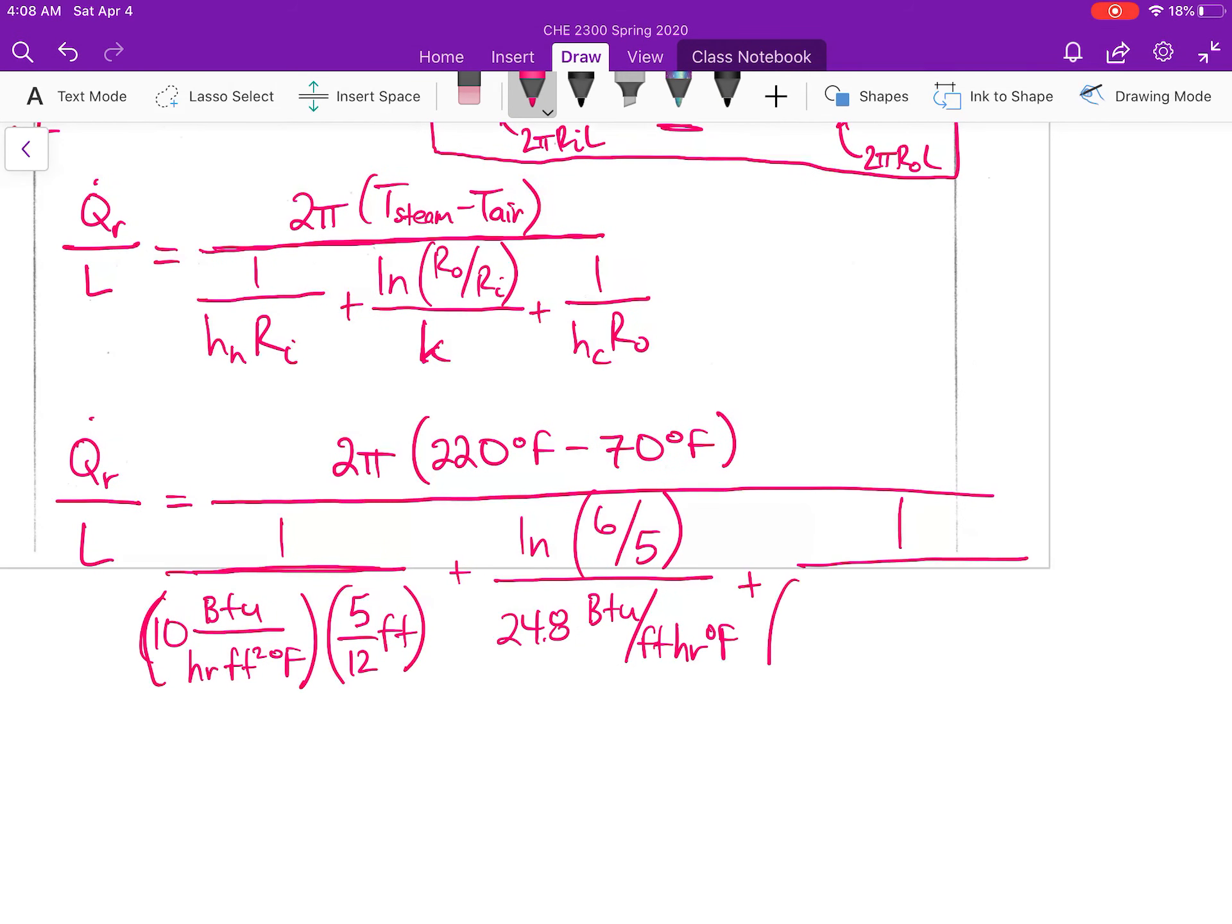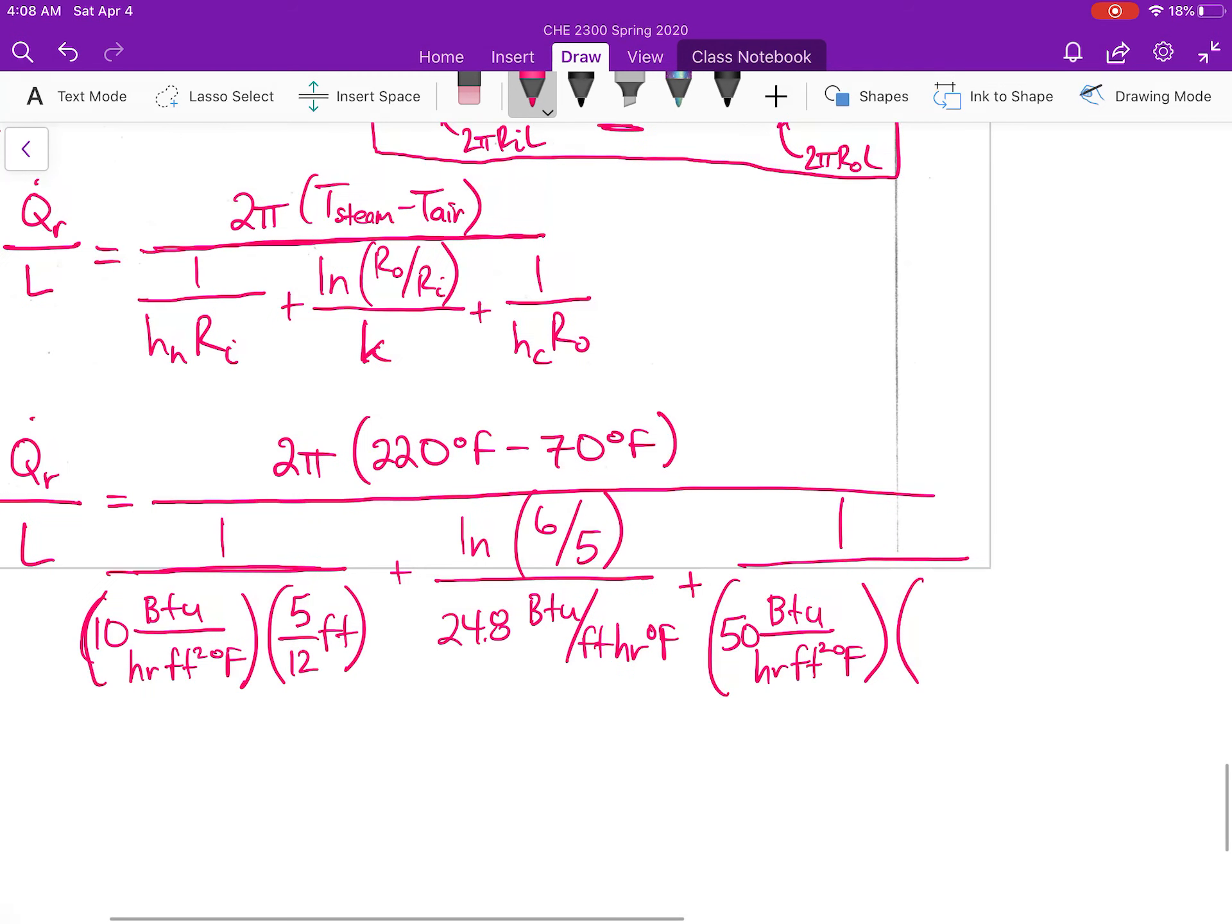Plus 1 over the convective heat transfer coefficient on the outside of the pipe, 50 BTUs per hour foot squared degrees Fahrenheit, multiplied by the outside radius of the pipe, 6 divided by 12.